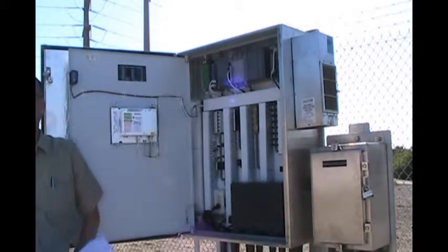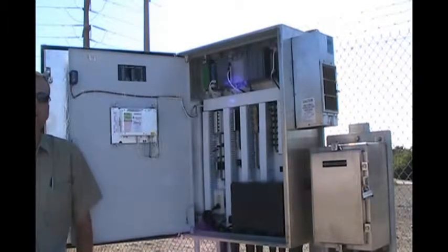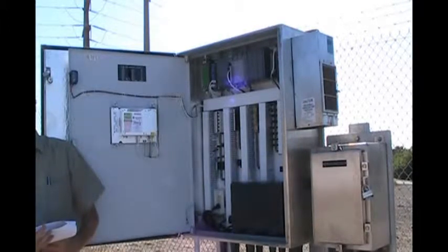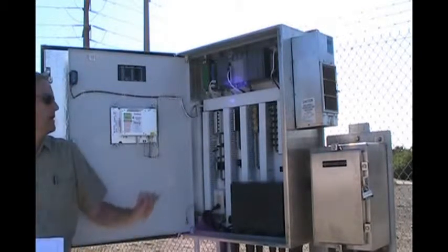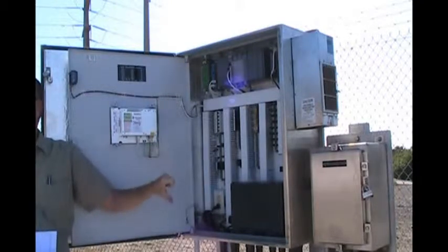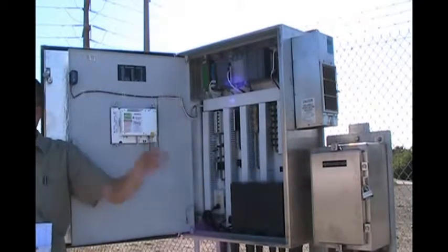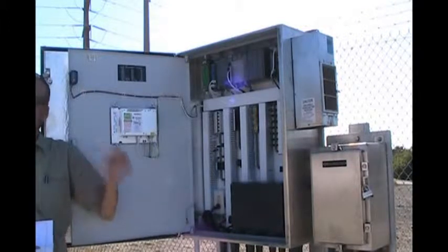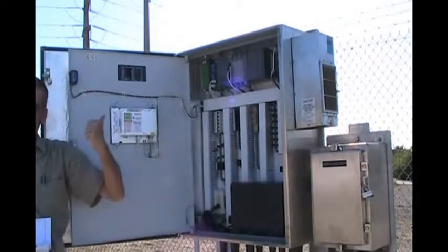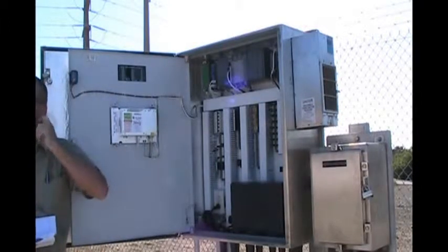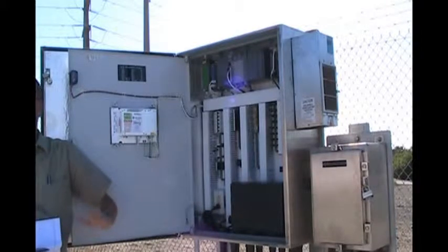If you have a signal that goes to a power failure, you're going to have a separate signal for the DC power and a separate signal for the AC power, because you could lose your DC power without losing your AC if your power supply went out. So you'll know DC power is what went out. If you lose your AC power, you're going to get a signal because your UPS is going to hold up your system for half hour to send a signal to your SCADA that it was the AC power that failed. So you'll get those signals, you'll know exactly what failed back at RP1.